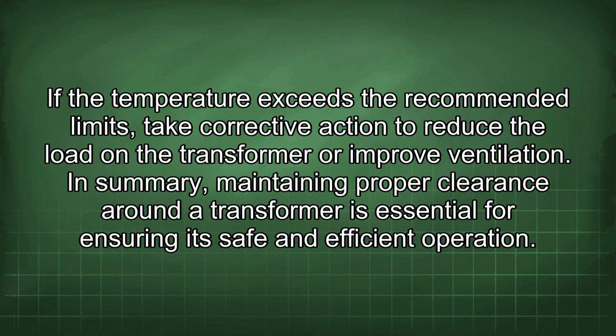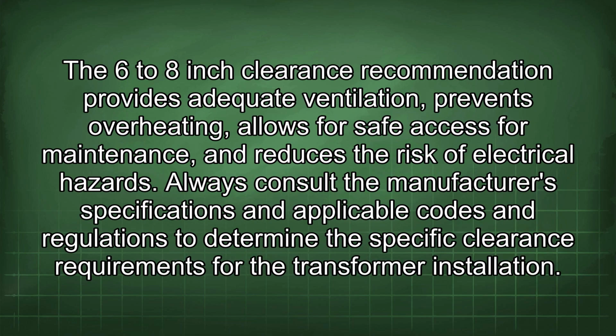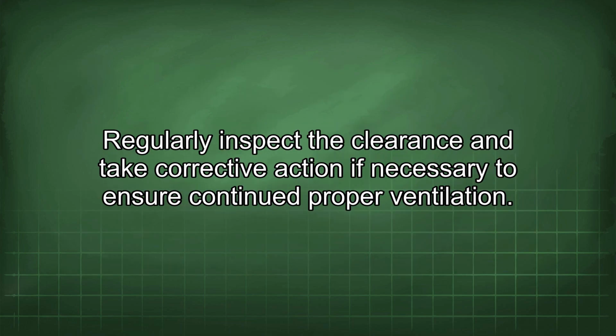In summary, maintaining proper clearance around a transformer is essential for ensuring its safe and efficient operation. The 6 to 8 inch clearance recommendation provides adequate ventilation, prevents overheating, allows for safe access for maintenance, and reduces the risk of electrical hazards. Always consult the manufacturer's specifications and applicable codes and regulations to determine the specific clearance requirements for the transformer installation. Regularly inspect the clearance and take corrective action if necessary to ensure continued proper ventilation.